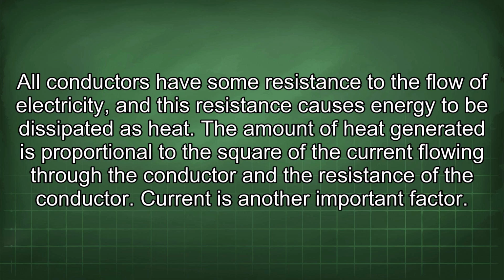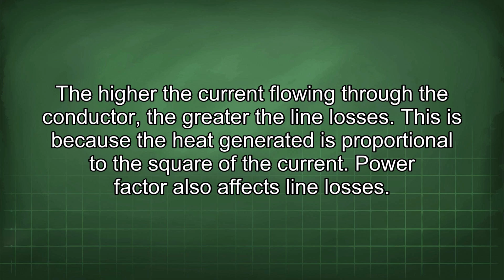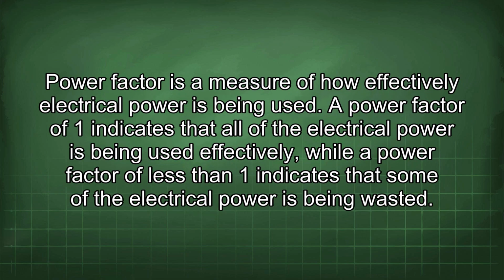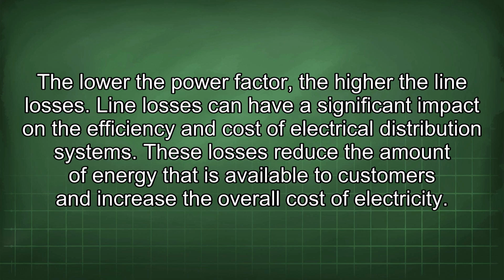The amount of heat generated is proportional to the square of the current flowing through the conductor and the resistance of the conductor. Current is another important factor. The higher the current flowing through the conductor, the greater the line losses. This is because the heat generated is proportional to the square of the current. Power factor also affects line losses. Power factor is a measure of how effectively electrical power is being used. A power factor of 1 indicates that all of the electrical power is being used effectively, while a power factor of less than 1 indicates that some of the electrical power is being wasted. The lower the power factor, the higher the line losses.